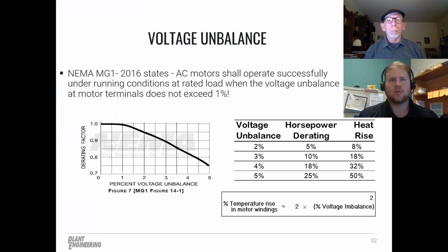In my job here at Advanced Energy, I work with utilities pretty often. When a facility comes online, they wire it up, and they may have a power purchase agreement in place. That's going to set limits on the amount of voltage imbalance that they provide, typically 2 to 3%. You may look at that and say 2 to 3%, that's not very much. But 2 to 3% in this case can be very detrimental to the motor population over time. The point to be made here is that even a very minor voltage imbalance can lead to horsepower derating for your motor.